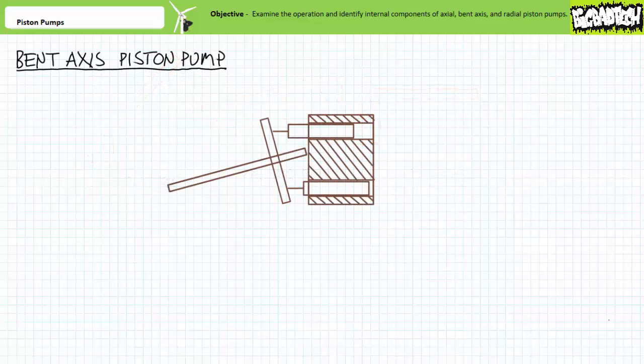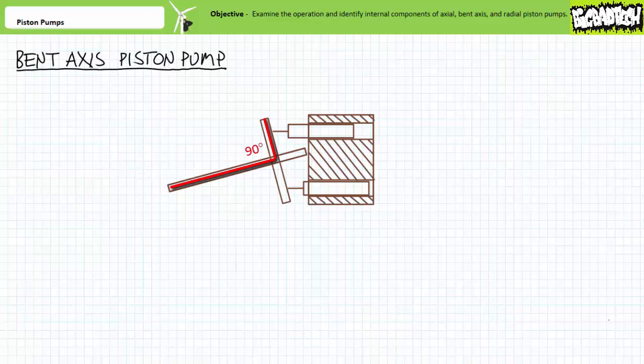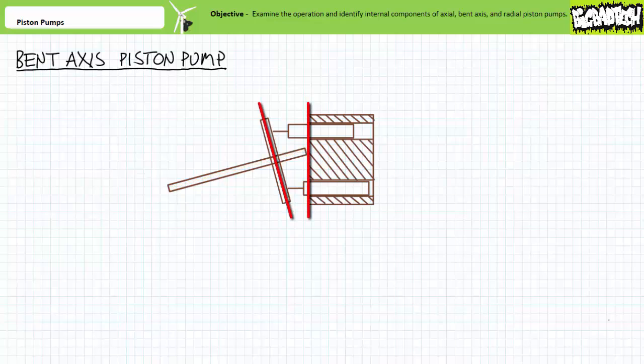Let's now briefly examine another type of piston pump known as a bent axis piston pump. A bent axis piston pump is really just a variation on the axial piston pump. Rather than having a swash plate held at an angle to the drive shaft, it has a swash plate held at a fixed right angle to the drive shaft. However, the drive shaft is now held at an angle to the piston block. If the drive shaft's angle to the piston block is fixed, this would be a fixed displacement bent axis piston pump.